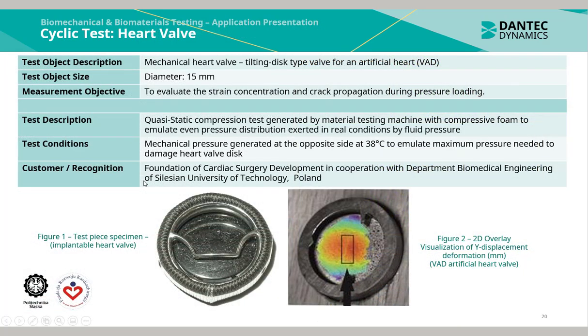The last application from the cardiac surgery elements is a cyclic test performed on a mechanical heart valve. This is a tilting disc type valve that can be found in an artificial heart or VAD. The test object size is 15 mm in diameter and the objective is to evaluate the strain concentration and crack propagation inside the valve during pressure loading.